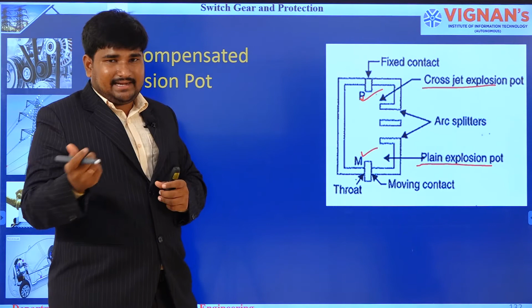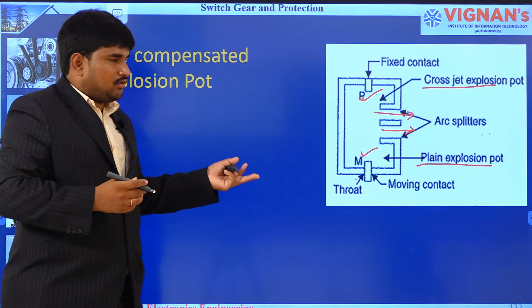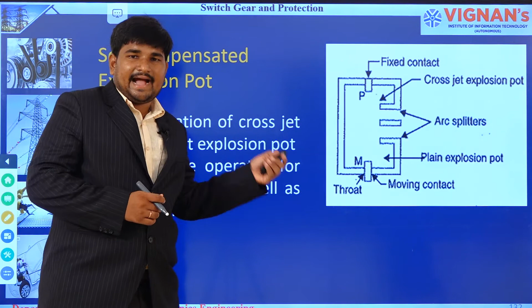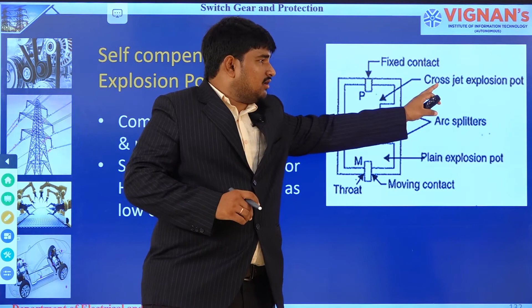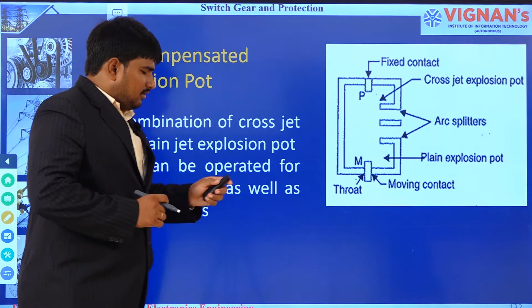Okay, for example, if you are using it for higher currents, the gas will be coming out from these arc splitters. This can be used for high currents as well as low currents because of this advantage, which is the combination of cross jet and plain explosion pot. Now, what are the disadvantages of bulk oil circuit breaker?